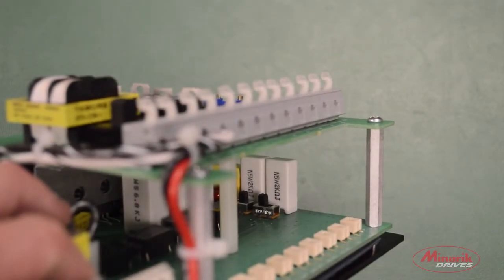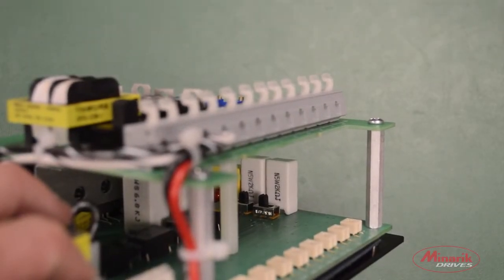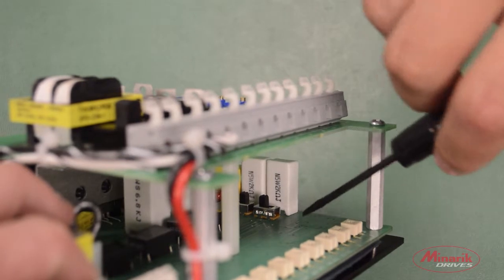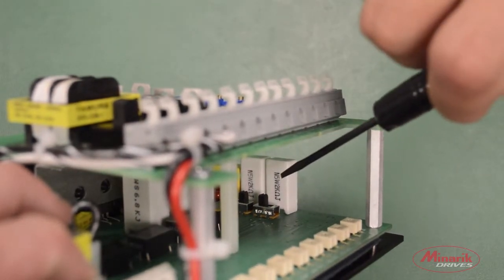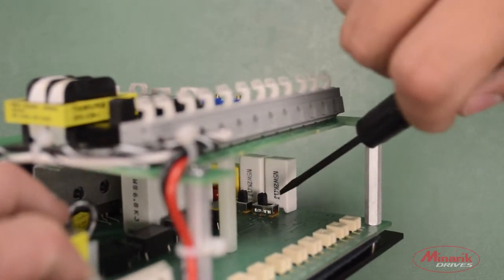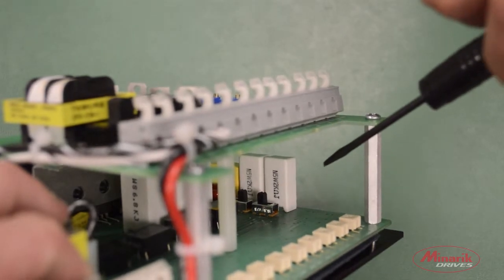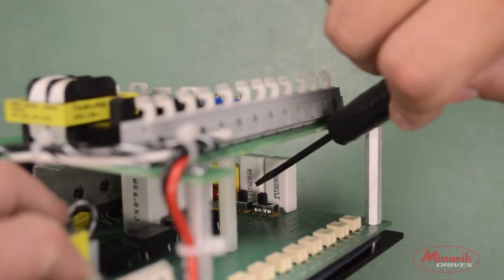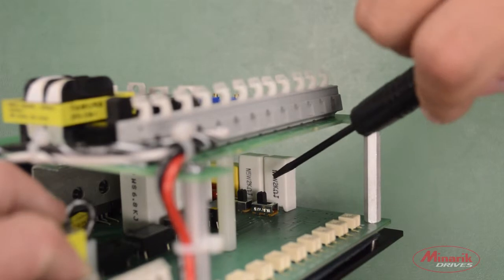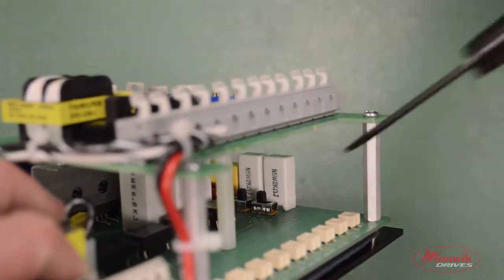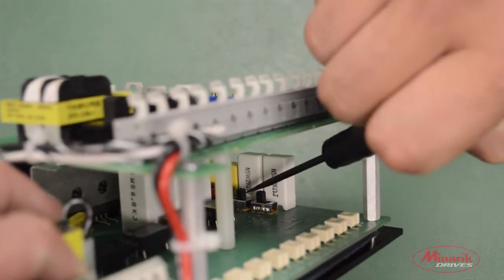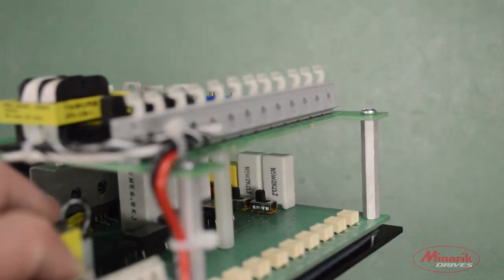Next, we're going to look at the output and feedback switch. The first switch is for feedback. It's factory default set for armature feedback. If you're using tach feedback, you'd have to switch it to the tach feedback position. The switch behind that is the output voltage switch. It's factory default set for 180 volts DC. We're using a 90 volt motor, so we'll switch it to the 90 volt position.